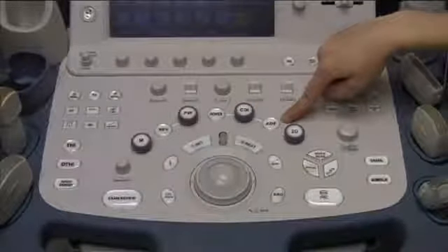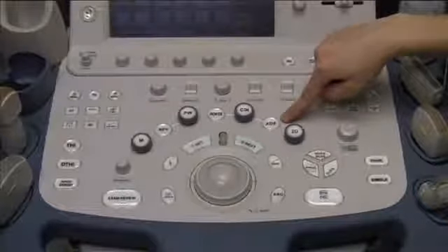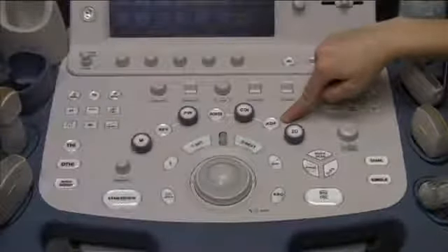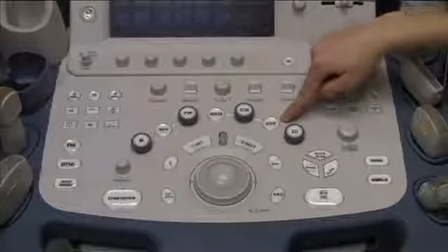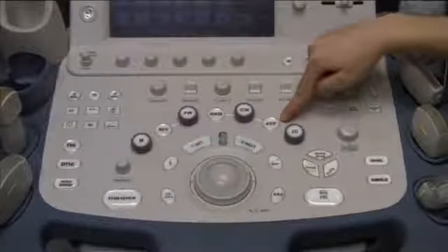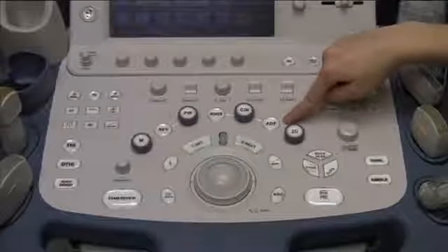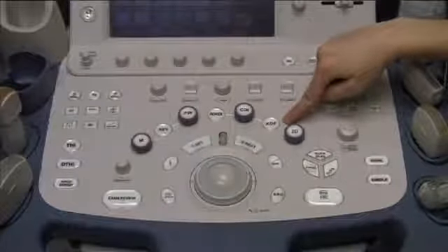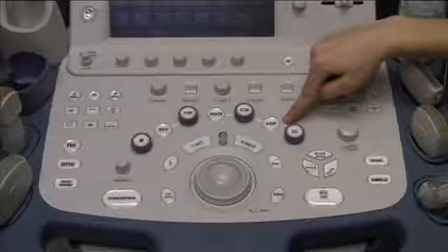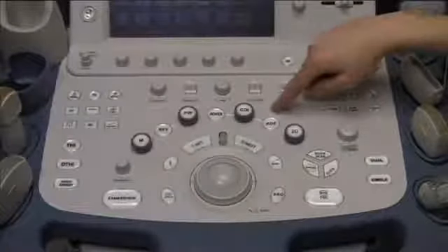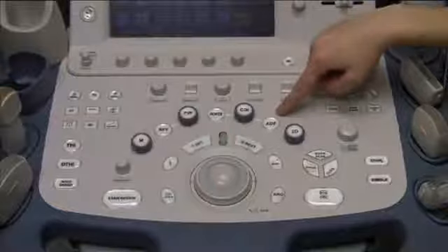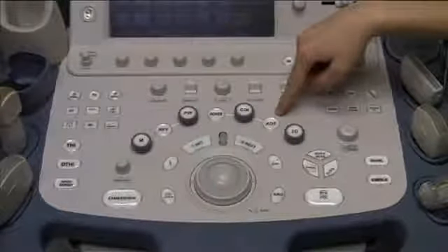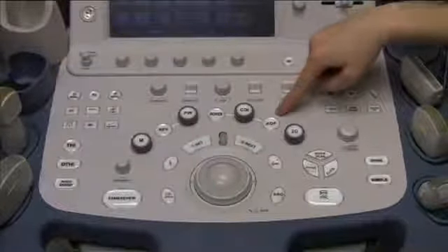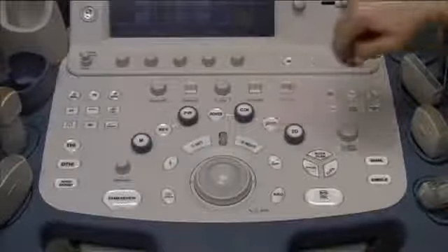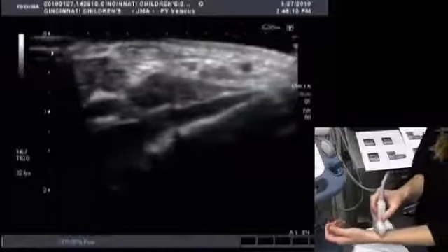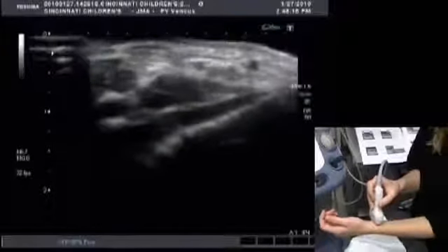ADF stands for Advanced Dynamic Flow. It's good for smaller vessels. It has a high resolution with a high frame sensitivity or rate. There's a lot less blooming than with CDI. This one, however, is very sensitive to movement artifact, so you would not want to use it in your pulsatile vessels. To use color Doppler, press Power, CDI, or ADF. For this demonstration, we're going to be scanning our radial artery, so we will use ADF. Press this button. Scan your wrist in the AP axis without pressing too hard or you will compress the radial artery.